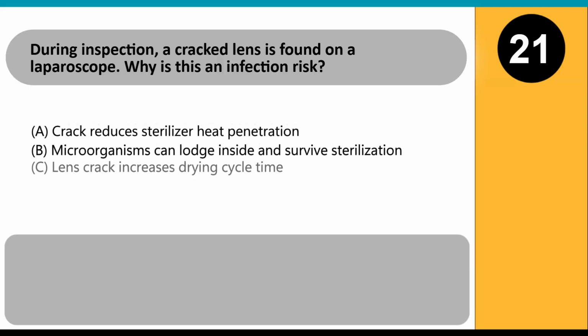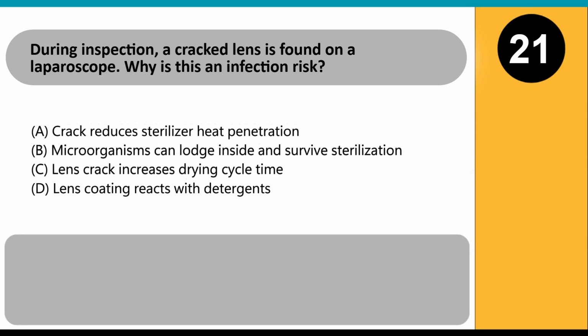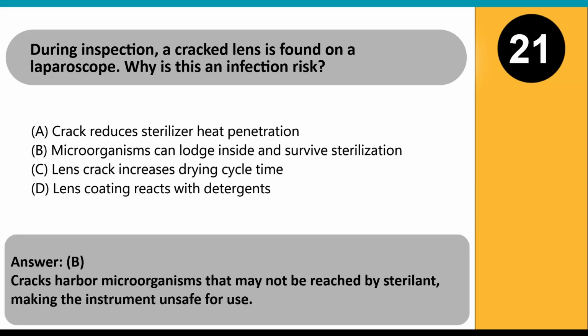During inspection, a cracked lens is found on a laparoscope. Why is this an infection risk? A. Crack reduces sterilizer heat penetration. B. Microorganisms can lodge inside and survive sterilization. C. Lens crack increases drying cycle time. D. Lens coating reacts with detergents. Answer: B. Cracks harbor microorganisms that may not be reached by sterilant, making the instrument unsafe for use.